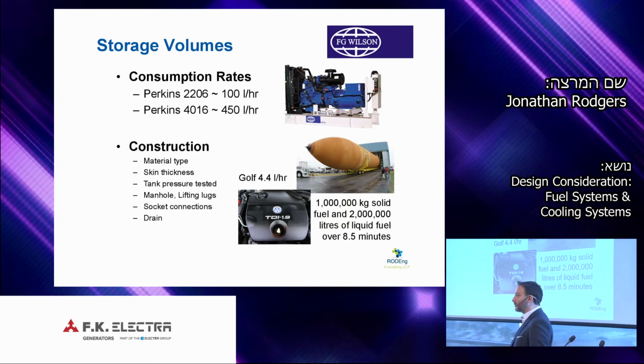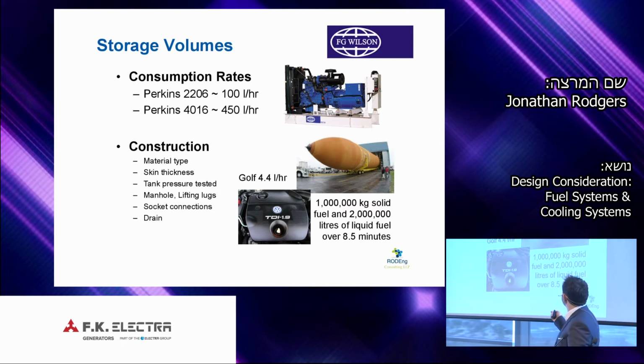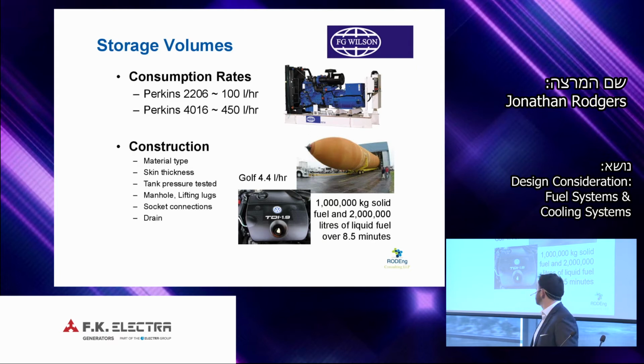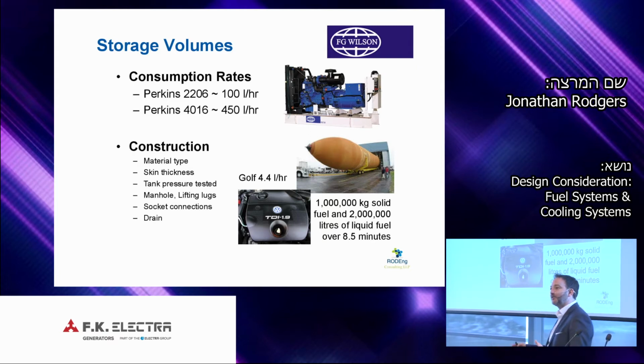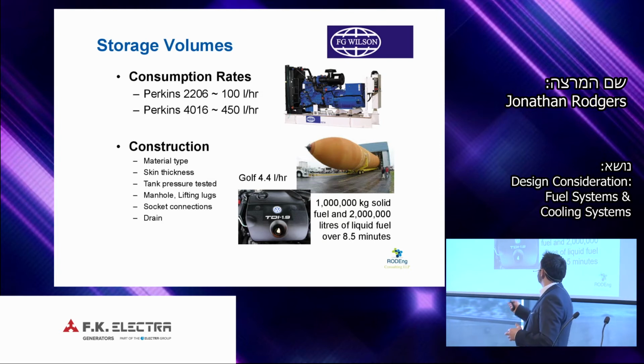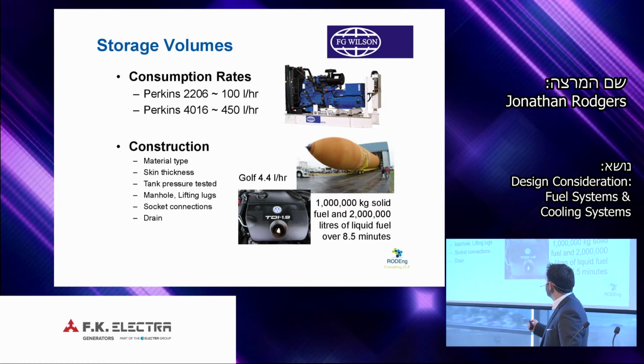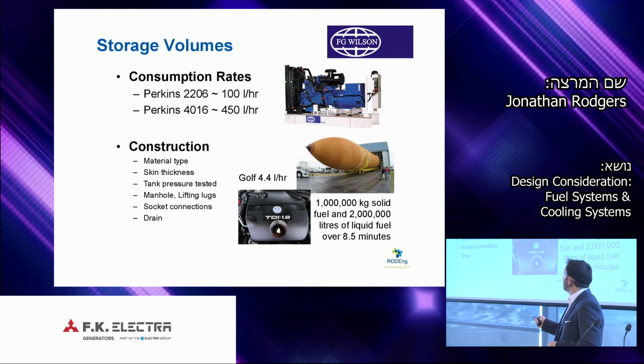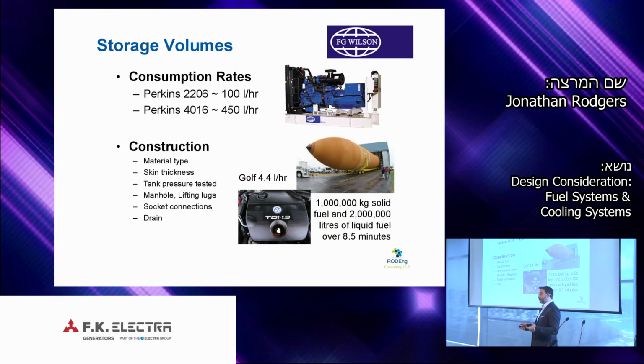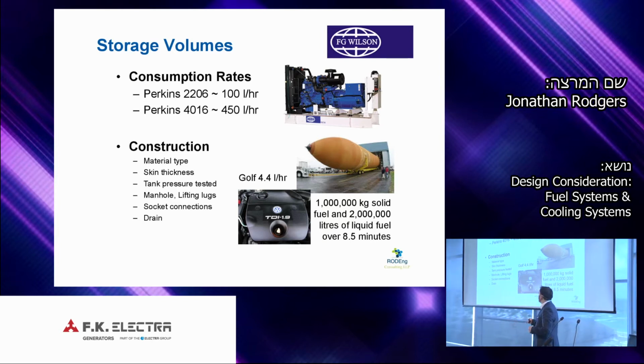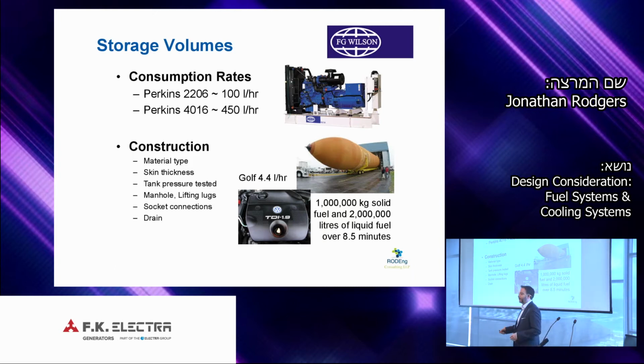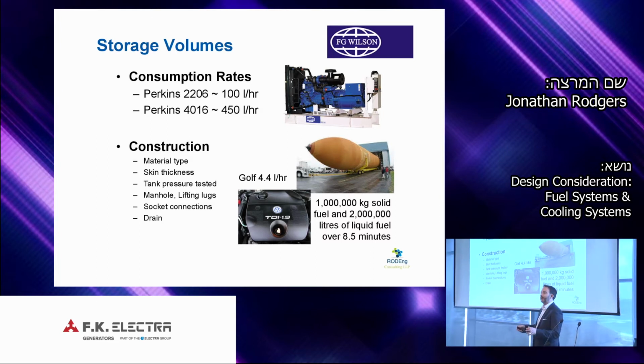And then if we look at large fuel storage, this is one of the space shuttle solid tanks, and we're talking around 1 million kilograms of solid fuel there. So we're in a range that's very much in between. So we have particular standards for the range of engine types that we're looking to design for generator applications. The one thing that is common, no matter what the type of fuel storage, is the construction of the tanks. We're looking at metals, thickness of metal, how they're joined, and pressure. Pressure is critical in all aspects of fuel systems, and particularly in tank design. And then all of the types of tanks always have to have an access, a means of maintaining or inspecting the integrity of the tank.